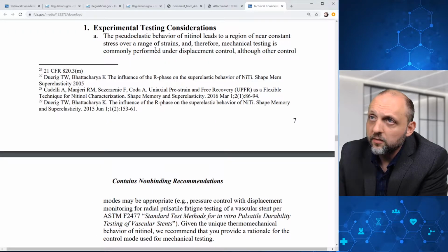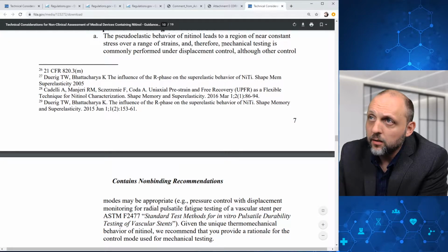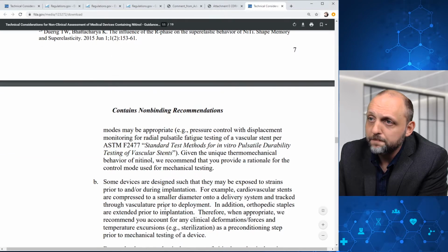Under experimental testing conditions, FDA here says that mechanical testing is commonly performed under displacement control, although other control modes may be appropriate. And given the unique thermomechanical behavior of nitinol, FDA recommends that you provide a rationale for the control mode used for mechanical testing.